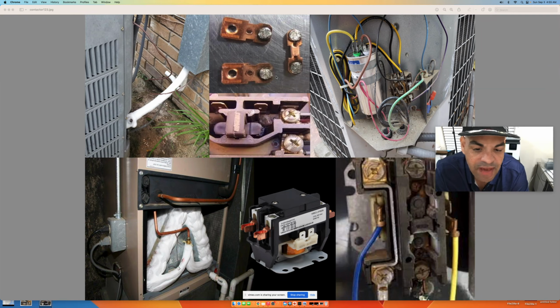Now, the other symptom is sometimes it's stuck, but then you've got voltage going across, and the voltage keeps on running continuously. Another way you can check this is to go to your thermostat and put it on off. If your outdoor unit is still running, that means that your contactor outside is stuck in the closed position, which means it's on. And what happens is the contacts on that contactor are stuck.